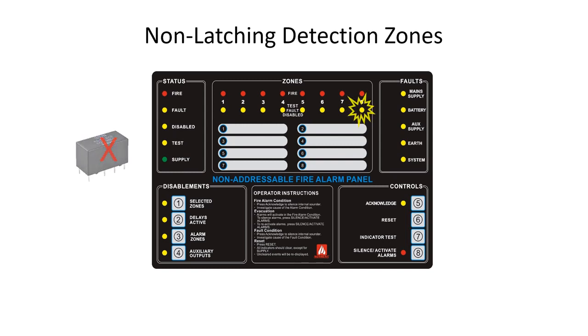To configure detection zones for non-latching operation, enter access level 3 and press the alarm zones button. The alarm zones LED and the acknowledge LED will flash. Press the acknowledge button to confirm. The alarm zones LED will be on. Use the silence activate alarms button to step through the zones.